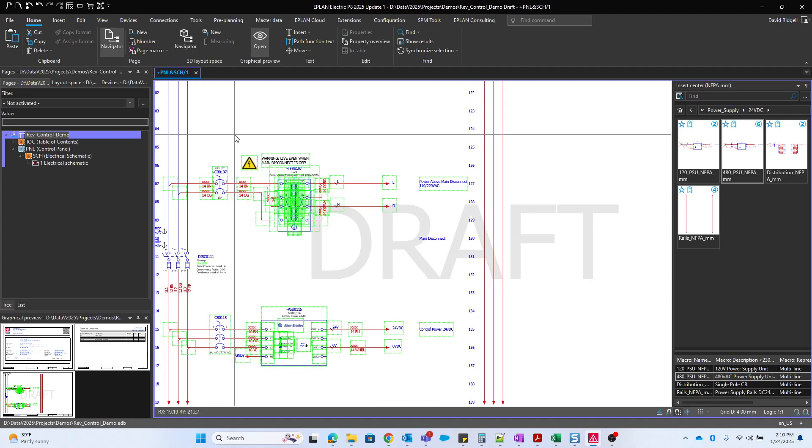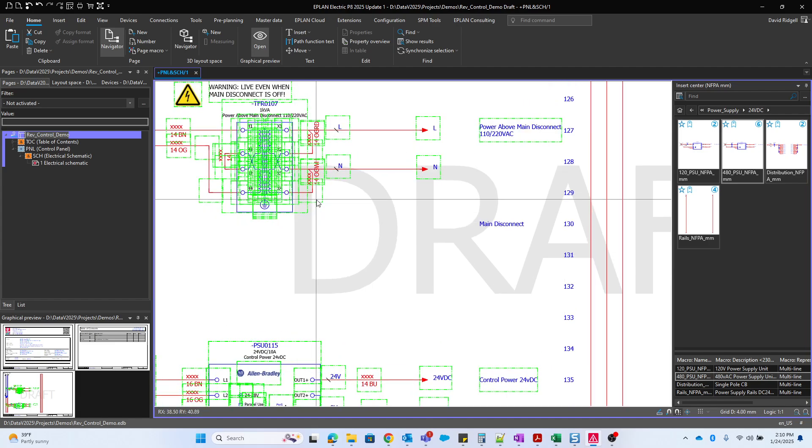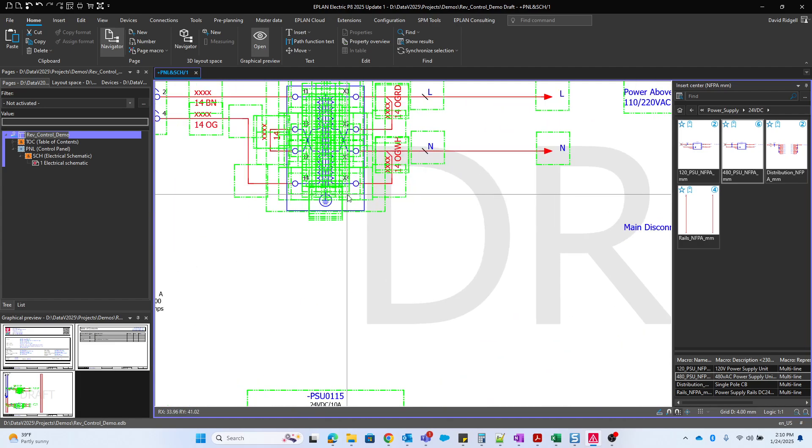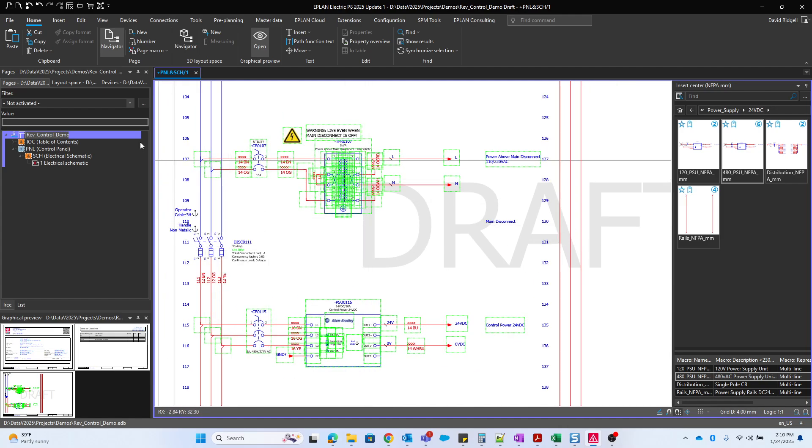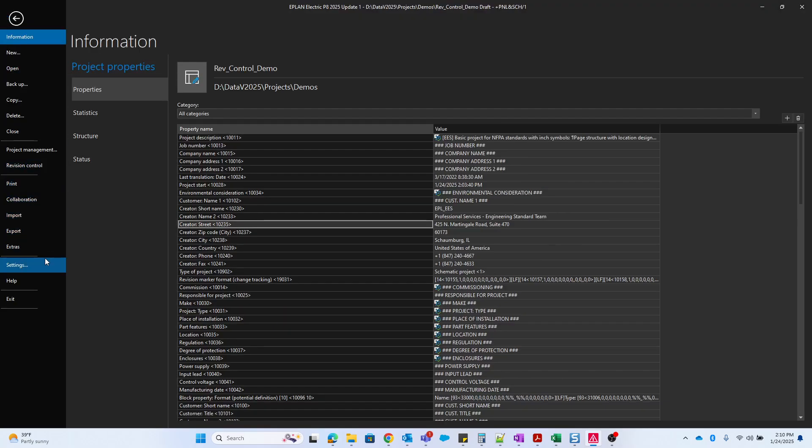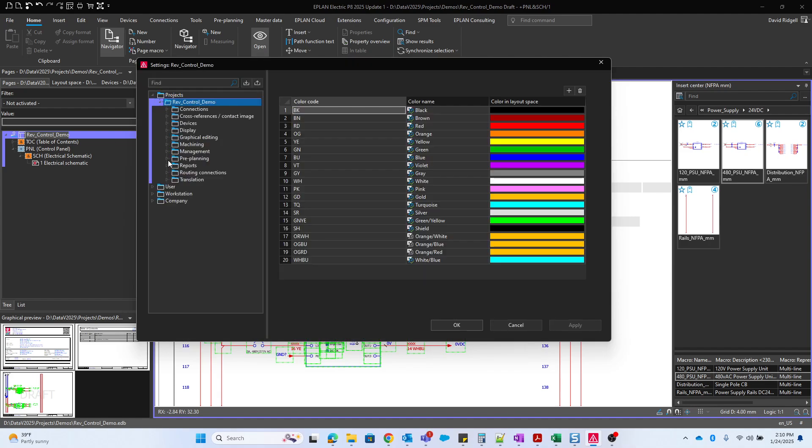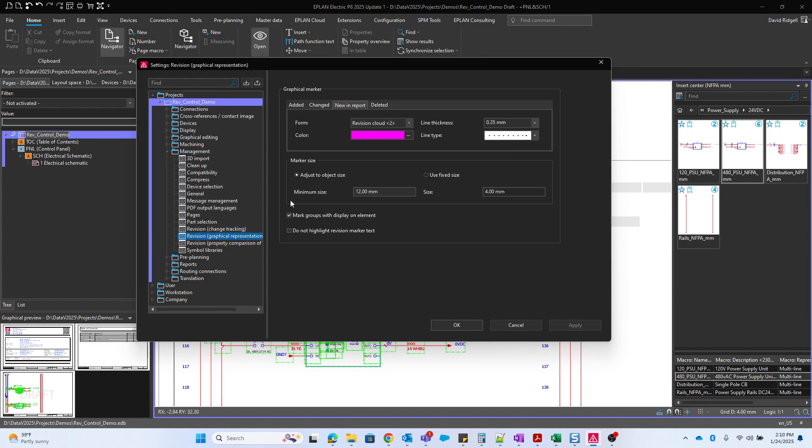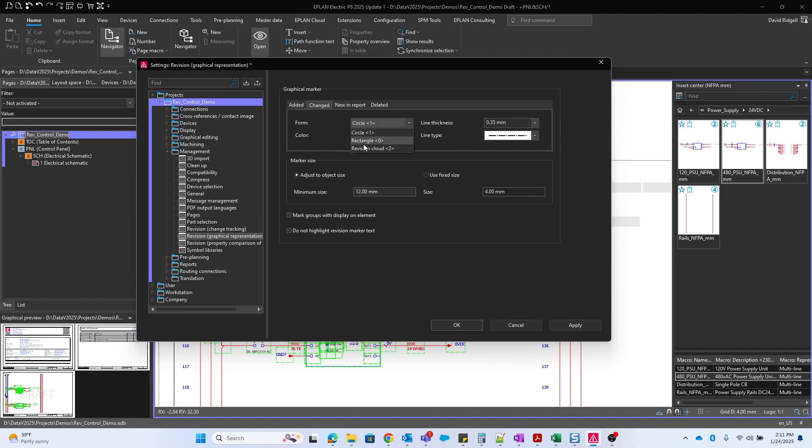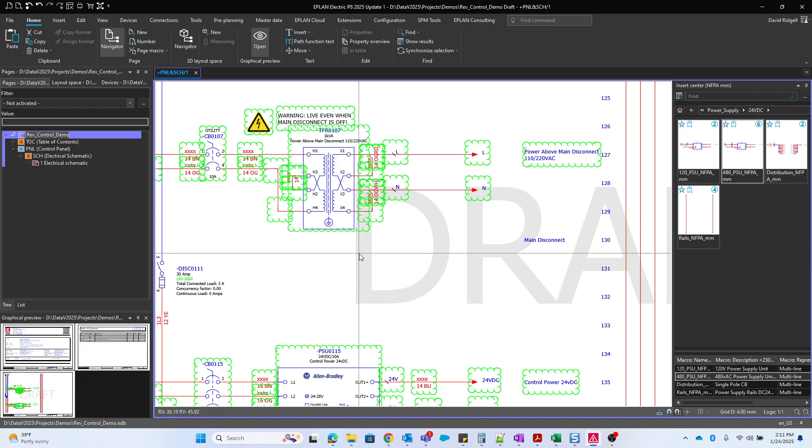So now I want to change the way that these different things look. I don't want these markers to be square and I don't want so many of them. I want them to be clouds. So this will be in the project settings. We'll go down to management and revision graphical representation and we'll change added to a cloud. And I'm going to uncheck this thing that says mark groups with display on element. Basically, what that means is if you have a group inside of ePlan, if that's checked, every individual item of the group will have its own marker. Whereas if it's unchecked, we'll receive one big marker. So in my opinion, it's going to look much cleaner if we just have that unchecked. And now hit okay. You'll see we've cleaned it up a bit. We don't have so many markers.